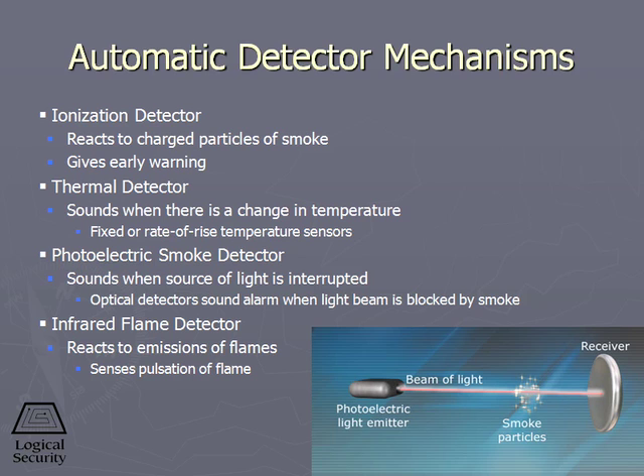fire detector. The next type of fire detector is a thermal detector. There are two types of thermal detectors. The first one is a fixed temperature thermal detector. This device says if the temperature ever exceeds, for example, 125 degrees, sound the alarm. That's a fixed value. The other type of thermal detector is called the rate of rise temperature sensor. This device says that if the temperature rises more than 10 degrees in a 1 minute period, sound the alarm. So again, two types of these thermal detections, fixed or rate of rise temperature sensors.